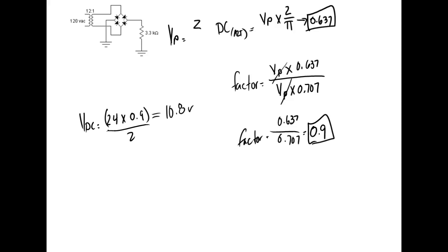So what we're doing is, if I rate my transformer at 120 volts, what's the odds of me getting 120 volts? What are we getting right here? We've measured it several times. What voltage do we have here? About 112, 113 volts, which is not 110 and it's not 120. But when I do my calculations, we're making approximations.